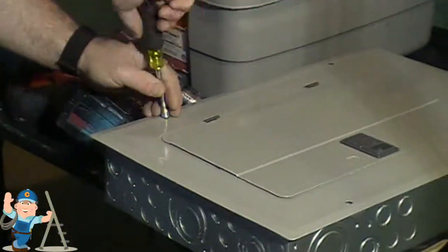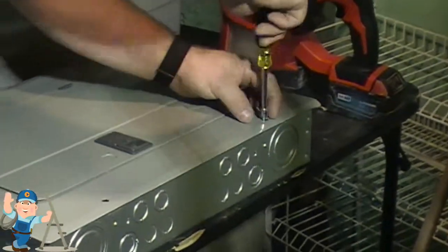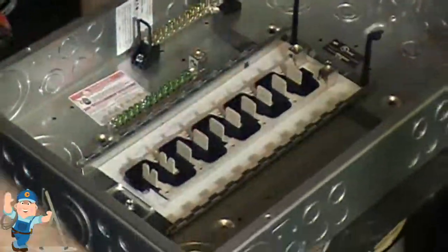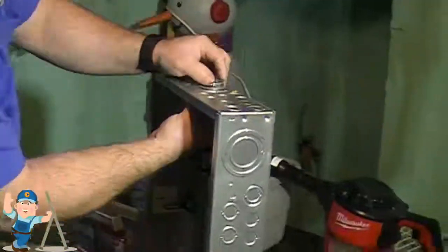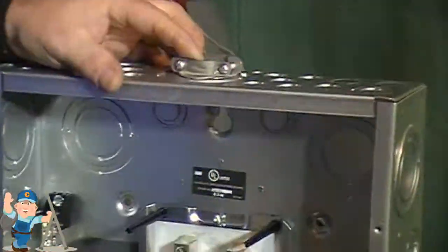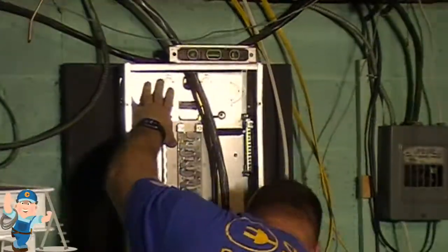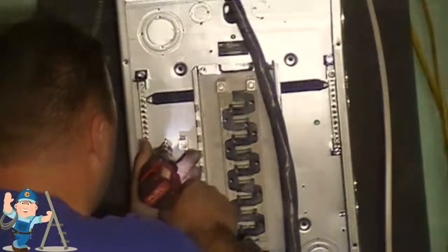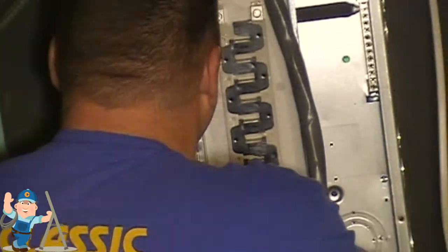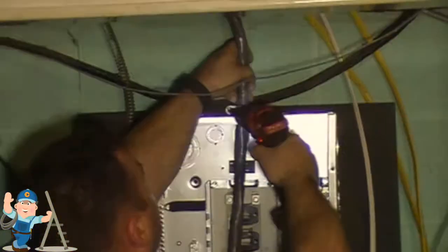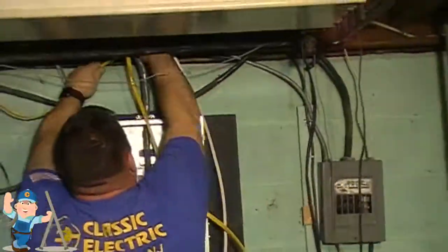So here I am with the 100 amp 20 circuit main lug only panel. There's room for actually 24 circuits on here with a couple of twin circuit breakers. So there I am putting in the connector for where the service entrance cable will come into the panel. I like to put that inside the connector as I'm putting the panel up. It's just easier to mount the panel this way and get the wire in there, less struggles. So I've been an electrician 27 years. I've done a lot of these, and this is the fastest way that I have found to get this done.